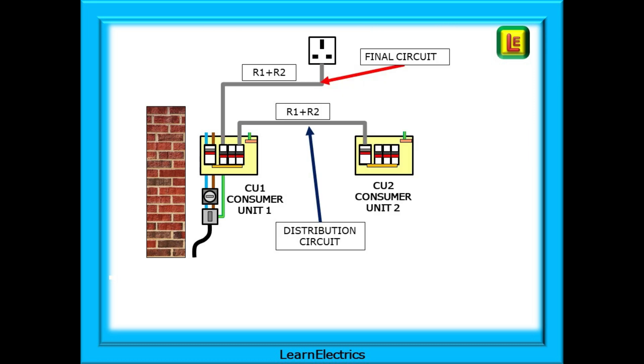Now we can add a second consumer unit which we've called CU2. This is supplied by a suitable cable from the circuit breaker in CU1, the consumer unit at the source of the installation. The cable between the two consumer units is called a distribution circuit.